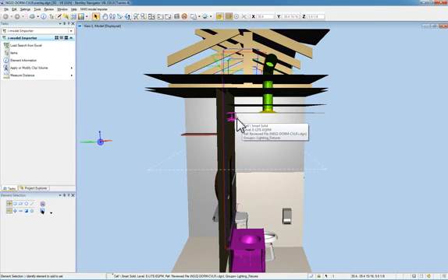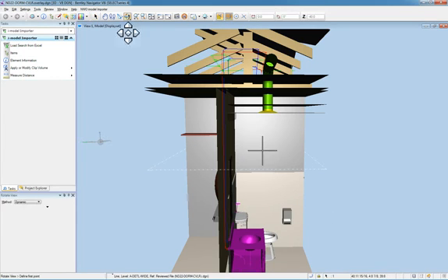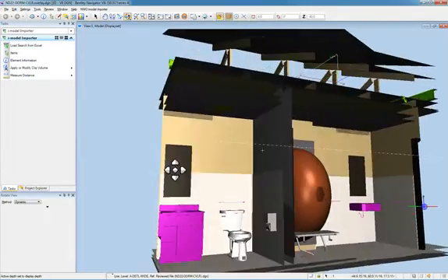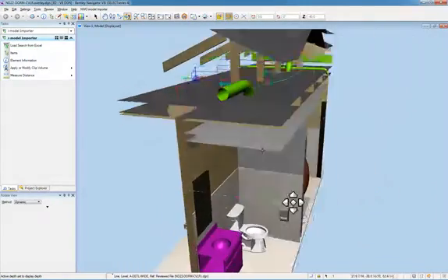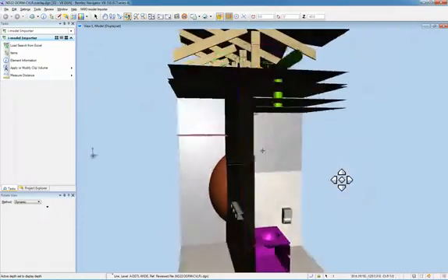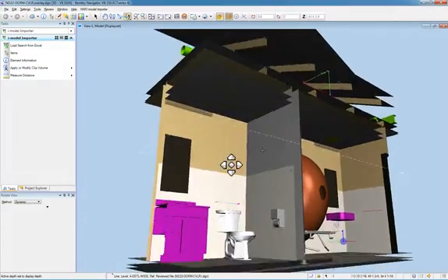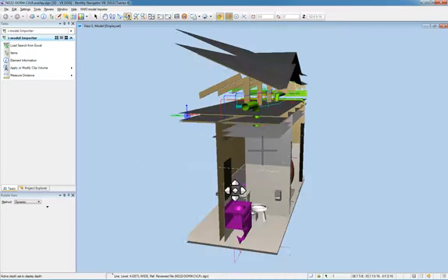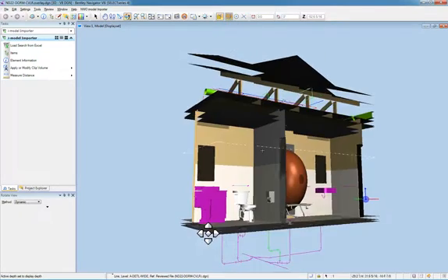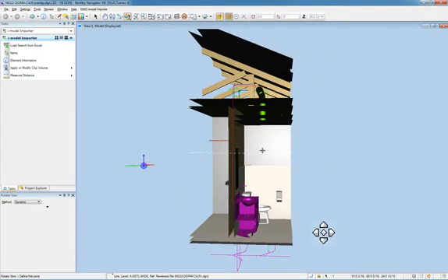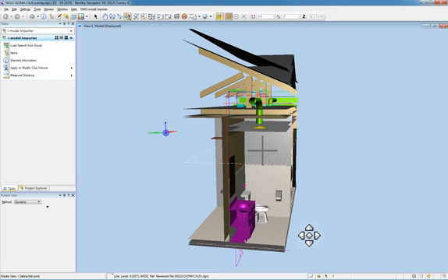I see something, E-LITE-EQPM. Light equipment might be a light fixture that they're trying to display with CAD information there. So really you've got to start paying attention, because you'll find that some designers won't spend the time to actually model the items in Revit or OpenBuildings Designer, but try to sketch something in to show up on their drawing. So you really want to be careful and make sure what is there and what isn't.